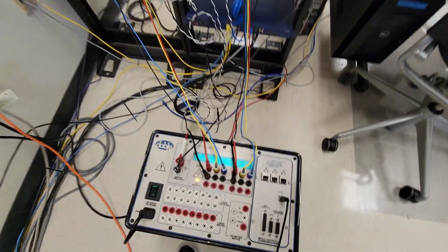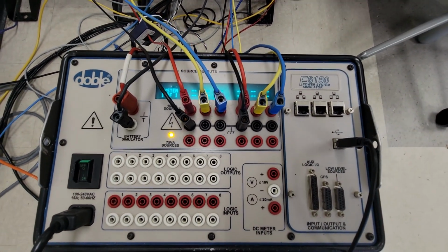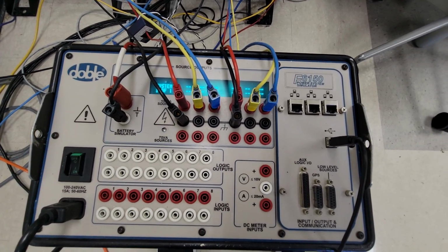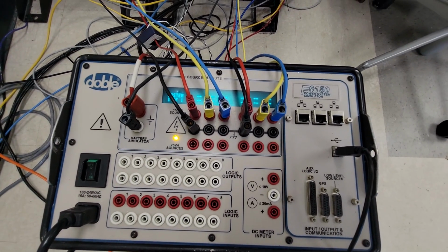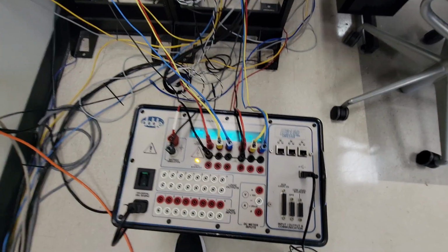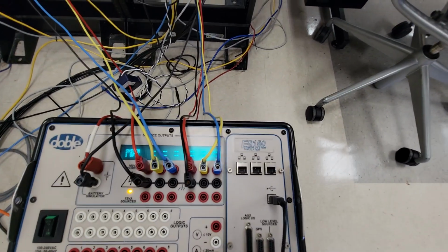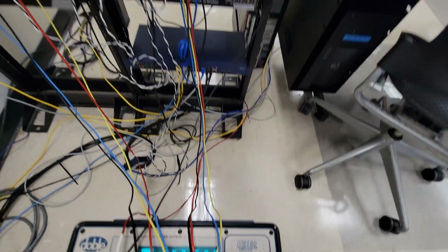And then you can also see we've got two circuits here. Red is A phase, yellow is B phase, and blue is C phase, and then the black is the neutral. This is a YY connection to both circuits. One of these is a current metered circuit, and the other one is a voltage metered circuit.